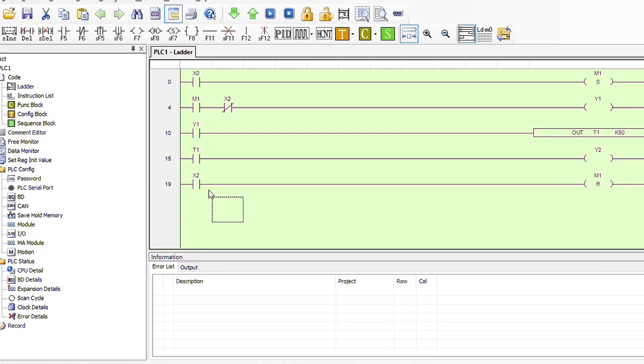The key point to understand is how a ladder program runs. Ladder logic is not executed like traditional programming languages. It runs from top to bottom and left to right. Top-to-bottom execution means that for a contact in the lower rung to activate, the conditions in a top rung must be met first. At the same time, logic can also be executed from left to right within a rung.